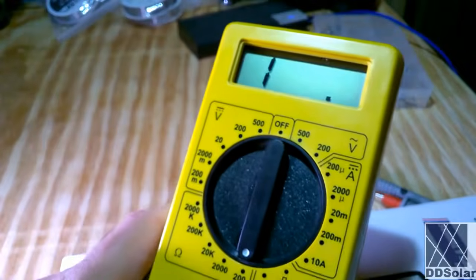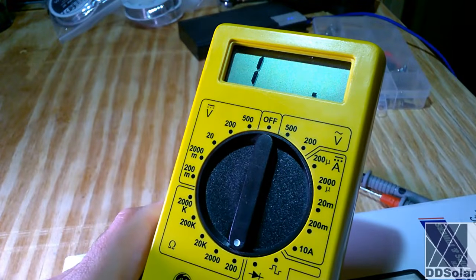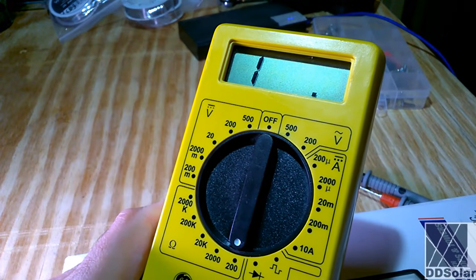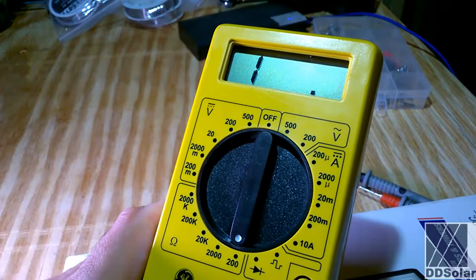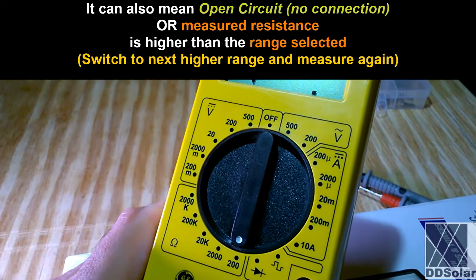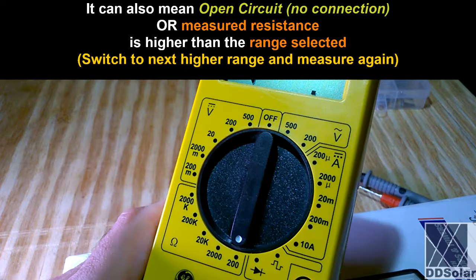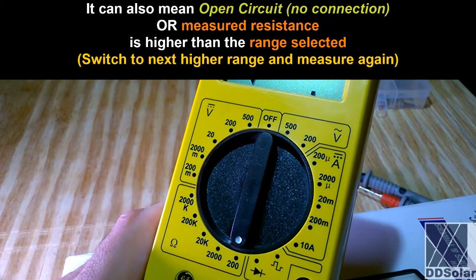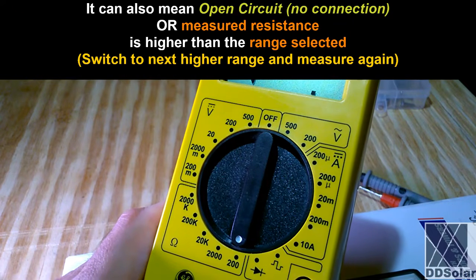And what will happen is the meter will, again, it should zero out. Now, different meters act different ways. Mine is a little bit odd. It shows a 1 and it shows a decimal place. It basically means, okay, I'm ready to take the measurement. Now, if you have a dead battery or there's something wrong with the meter, it may do something odd. I know this meter well, and I know it's ready to measure resistance.